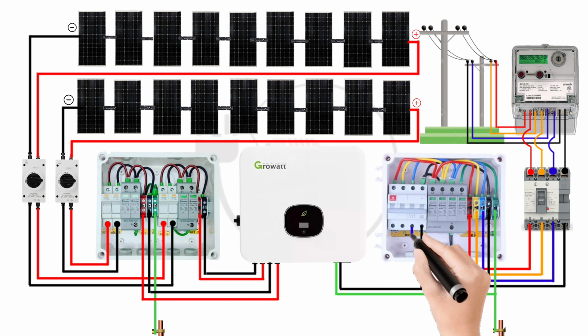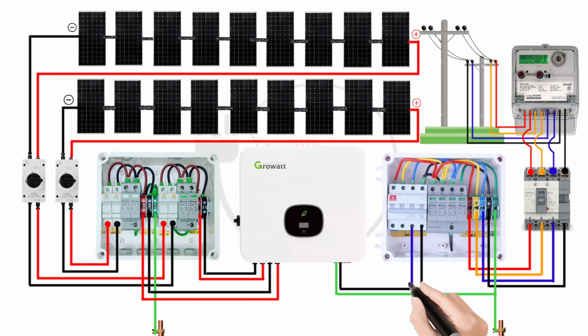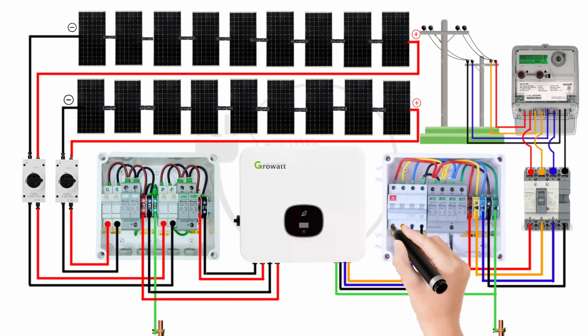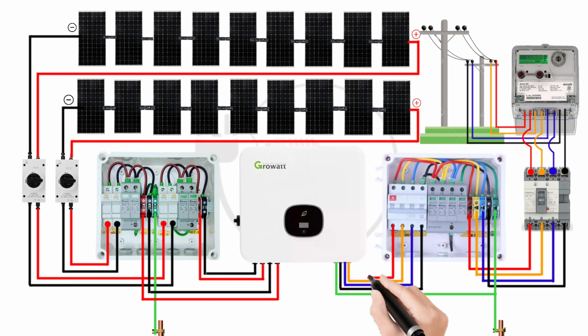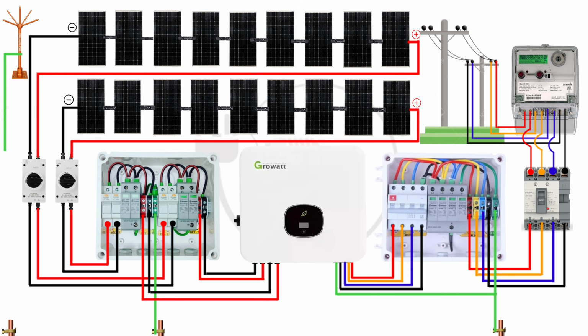Make sure the MCB is rated appropriately for your 10 kW system. Finally, the output of the MCB is connected to the AC input terminals of our 10 kW inverter. The inverter converts DC electricity generated by the solar panels into AC electricity that can be used by your home or fed back into the grid.